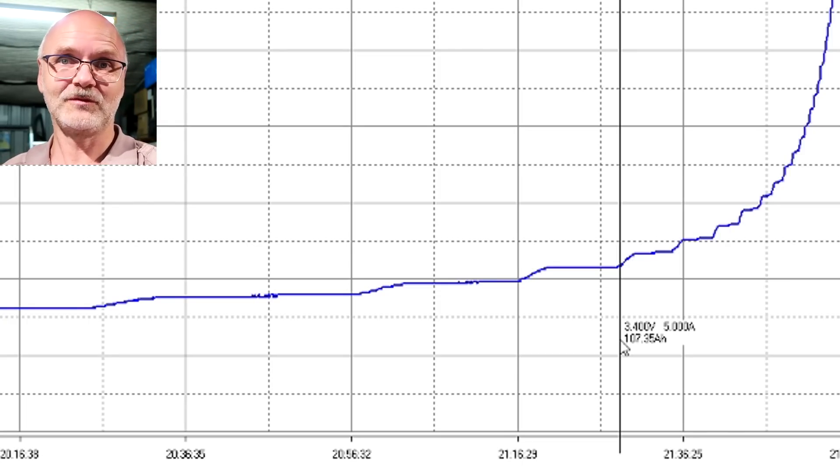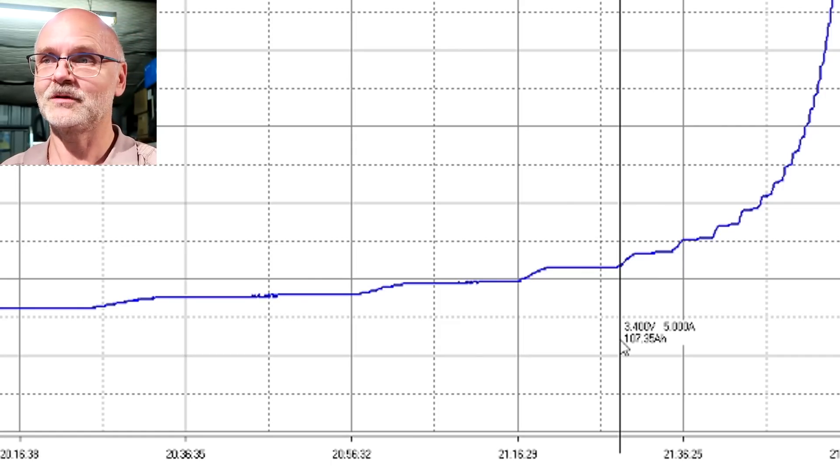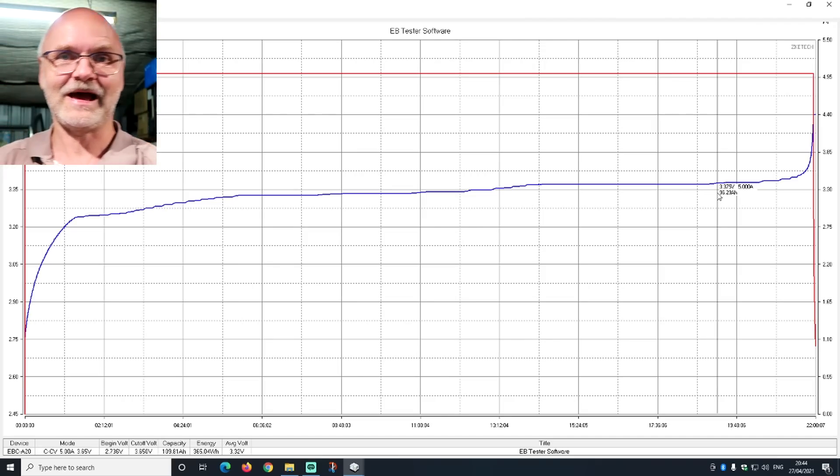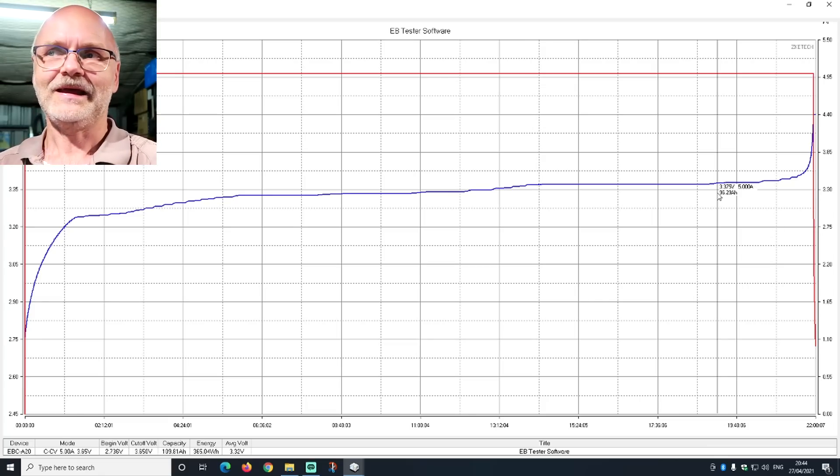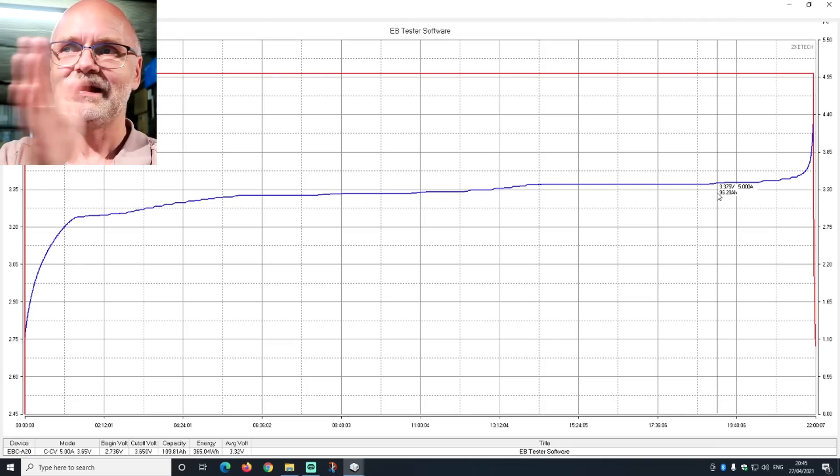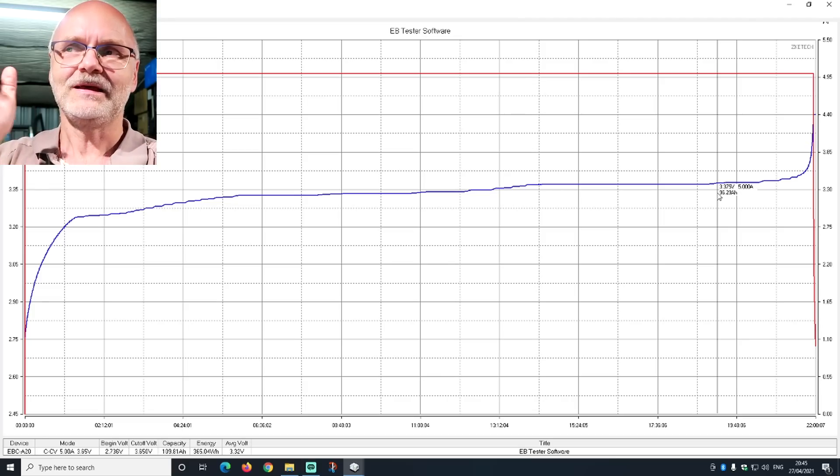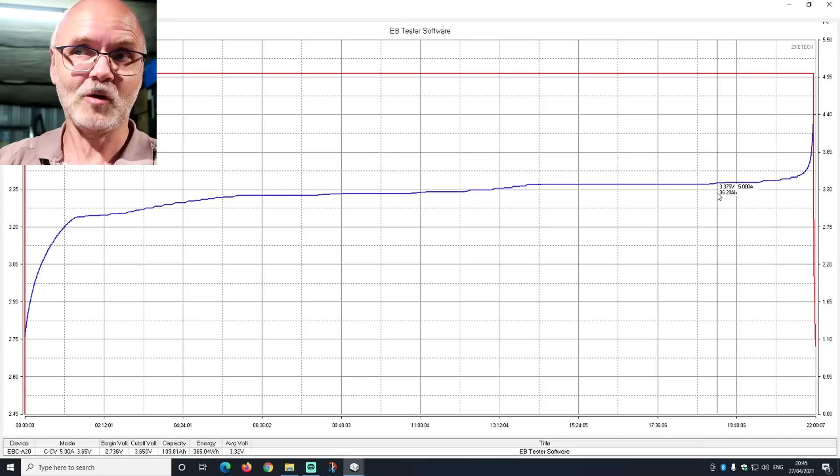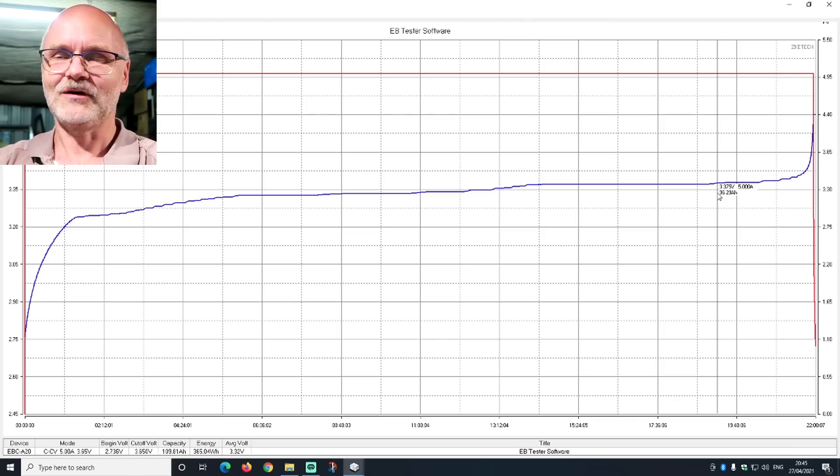So I don't really understand why we are doing that. But I will find out with the help of this setup here. We can now find out what is going on. So if we call it here, we've got 90% state of charge reached. Charge curve of course. And then I would like to know how much capacity do we actually have from this point. This charging to say 3.1 volts. How much does it give us? And then the next test would be charging to this point again. But then absorb. Let the battery absorb until the current goes to zero. How much more capacity would we gain without increasing the voltage. So these are some of the tests I would like to do with the software here. And get some nice graphs. And actually understand what is happening.